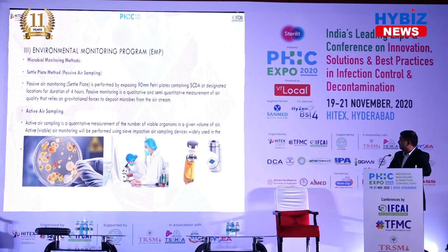The third picture is an air sampler, which is used for active air sampling, and 1000 liters of air is monitored by active air sampling. For air sampling, one instrument is used, which is called an air sampler, and 1000 liters of air, that is 1 meter cube of air, is monitored in a certain duration of time. Generally the monitoring duration is around 5 minutes to 10 minutes.